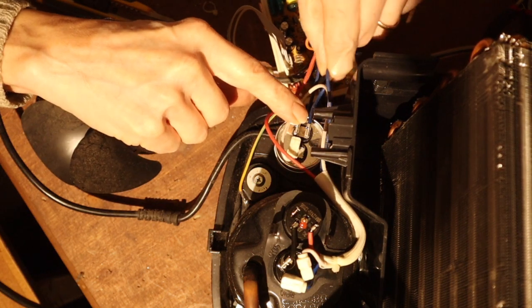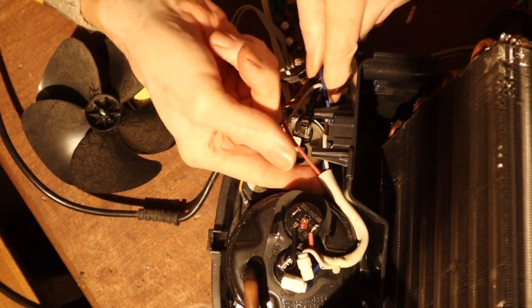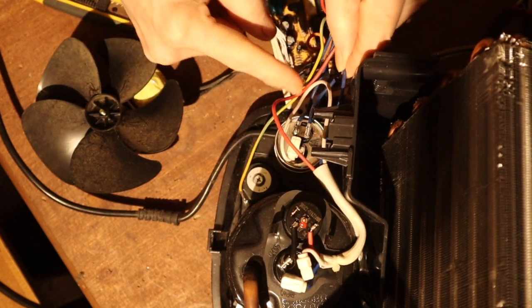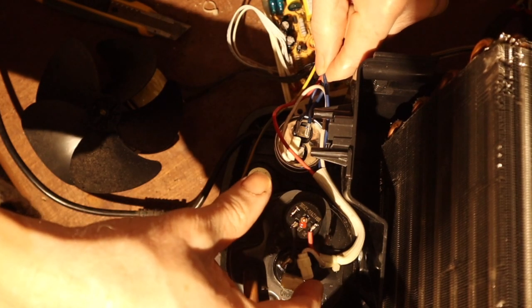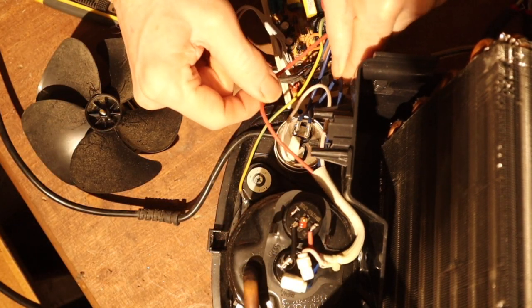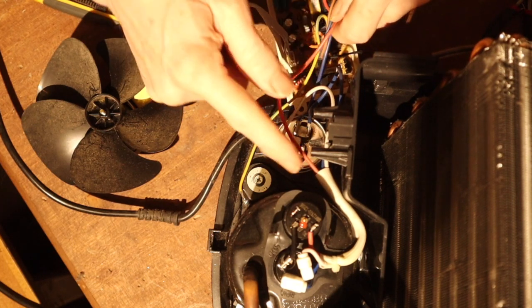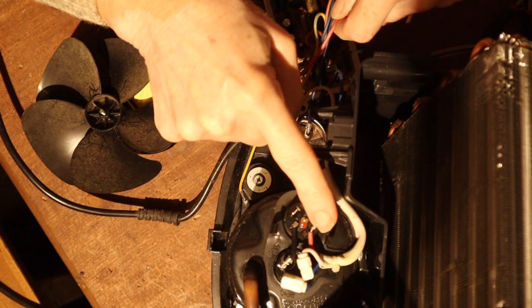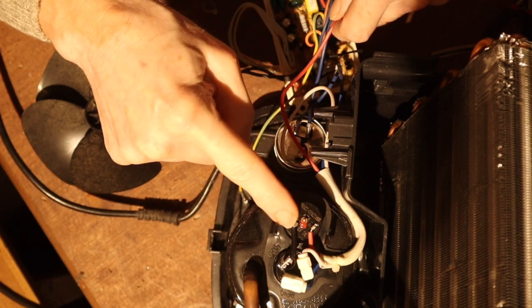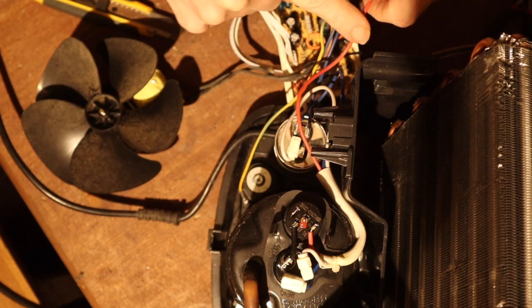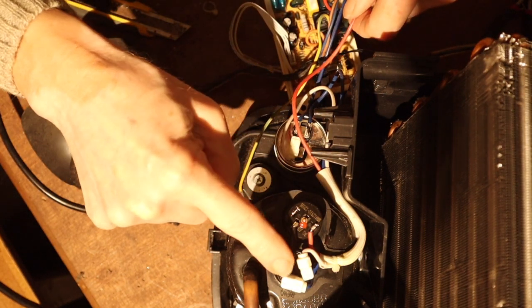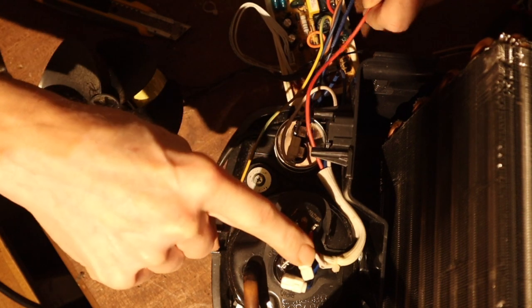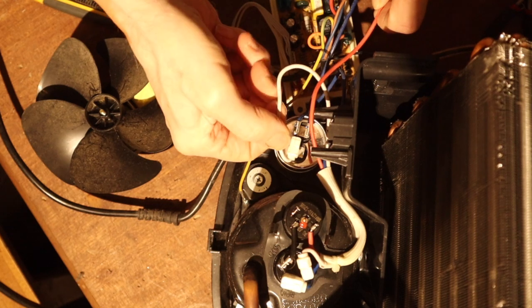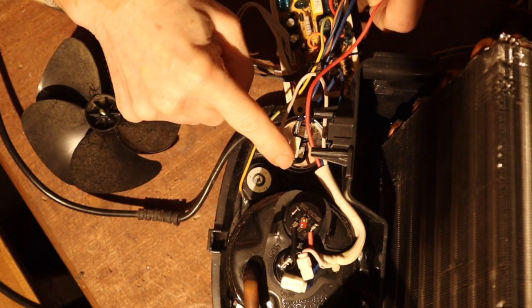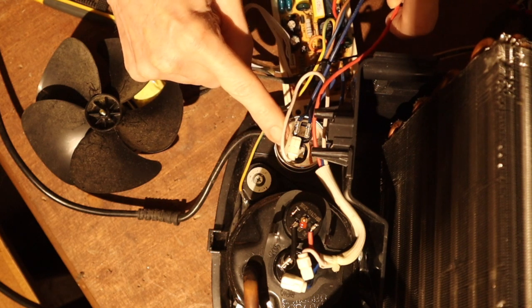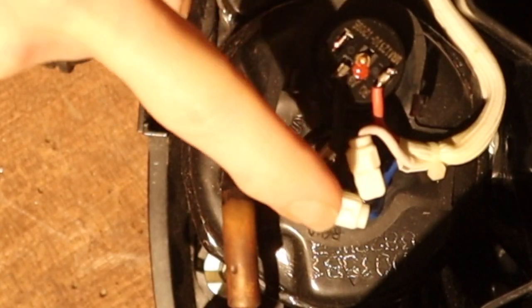Okay, we follow this, and this goes to this cable, to this combined cable. This blue one goes to here. And then there's a red one that goes to here, and this is of course the overload switch, and it goes to here. So practically this red wire goes to here. And then you have still this white cable, and that goes to this contact, so this white cable goes from the compressor to here. So that means the capacitor is connected between these two contacts.